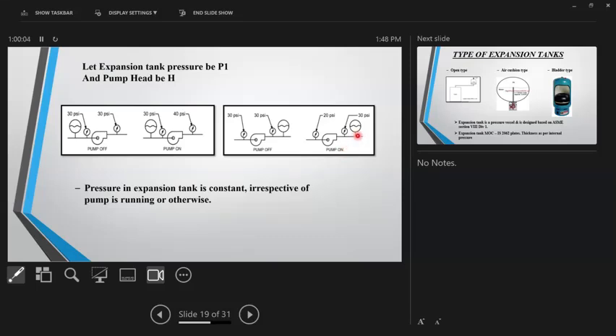So in any case, whether the pump is running or not running, whether the expansion tank is on the outlet or at the inlet, at a given temperature the pressure in the expansion tank always remains constant. That is why the expansion tank pressure is also known as a reference pressure. At all other points, there'll be changes.